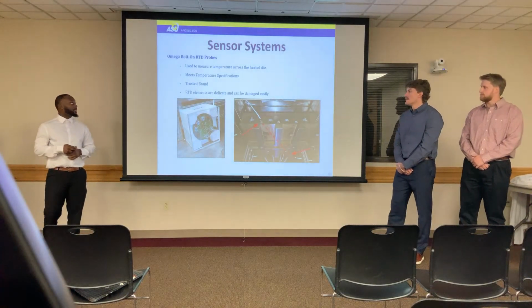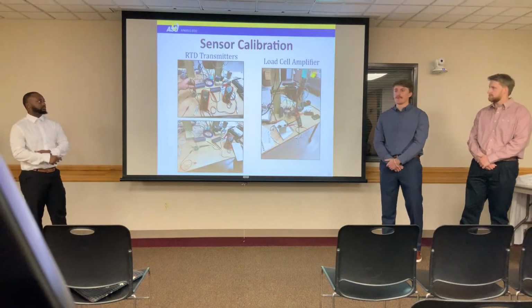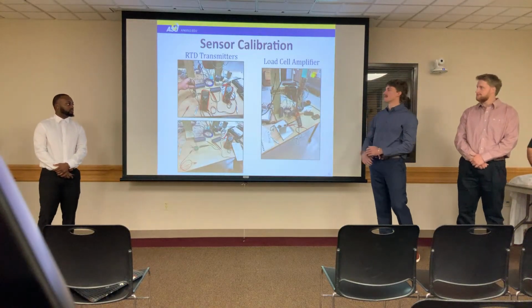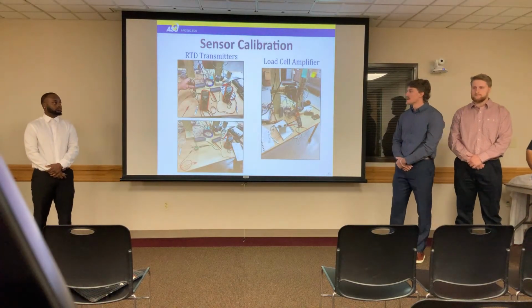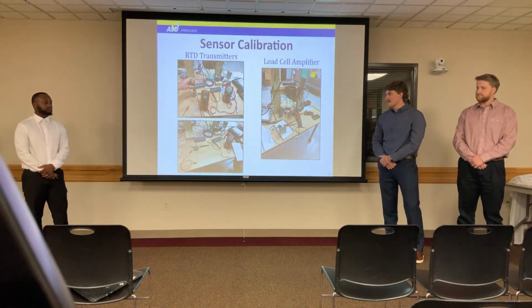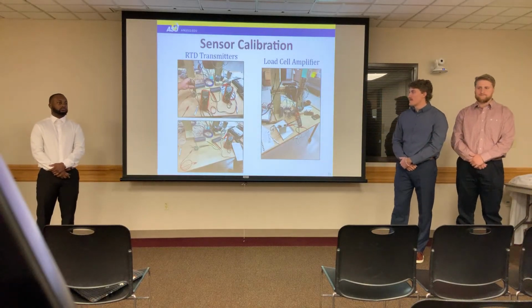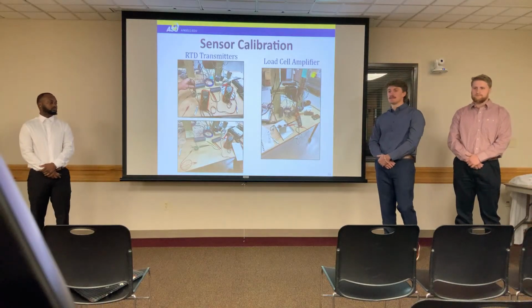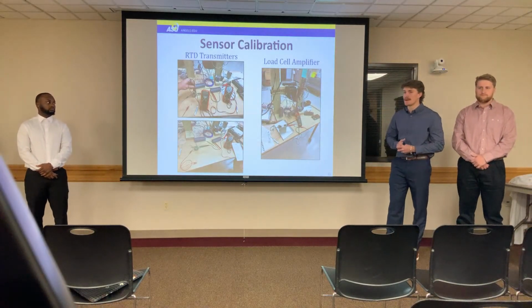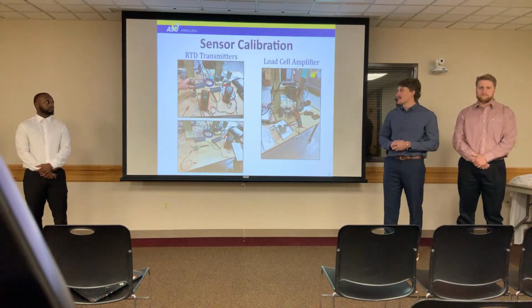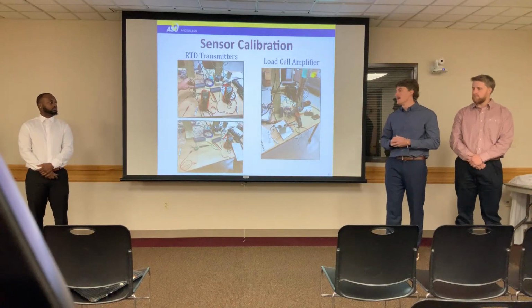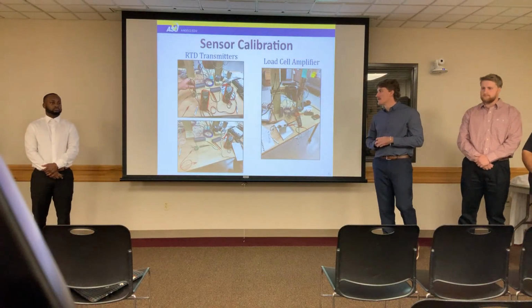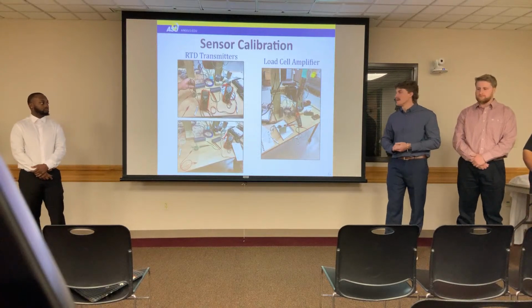All right, so moving into sensor calibration, we're gonna start with the RTD transmitters themselves. Basically, those RTD transmitters are taking the feedback from the RTDs, those resistance values, and then converting that to a 4 to 20 milliamp current reading, and the 20 milliamp being our high value, and the 4 milliamp being our low value. This process took about a week.